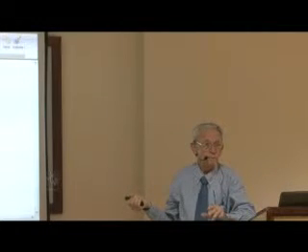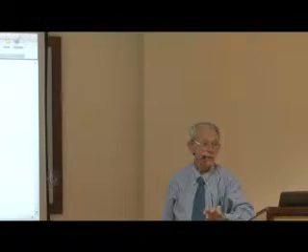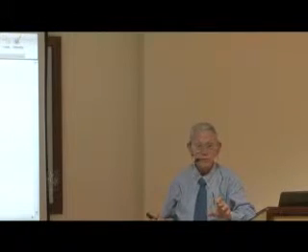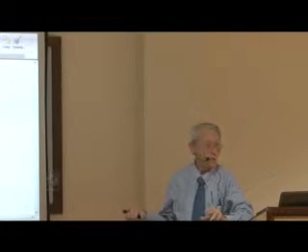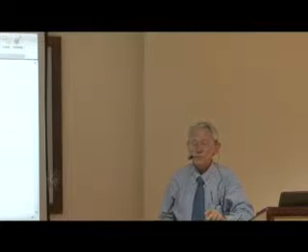So what shall I do? Well, then it's the next level up to check you and say, you're correct. Your analysis is correct, that the switching task you were given and the constraints you have to work within are not possible. It won't work. So, you've approached the solution. You said, forget the emergency bus, and I can do the switching. And maybe that's the only option that either of you can see. Then it's his job to go to management and say, we have to do the switching. We'll have to do something about the emergency bus.